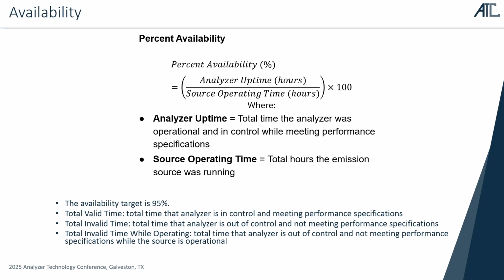So the first hour that you're doing the analyzer validation, and validation and calibration are used interchangeably, but really it needs to be daily validation, and then if you fail it, then you calibrate it. For the daily validation, you usually have about 1 hour that you can run without affecting your availability, but obviously you can't just be validating for the whole day. You actually need real measured data from the stack that is quality assured, which is the whole point of a CEMS.